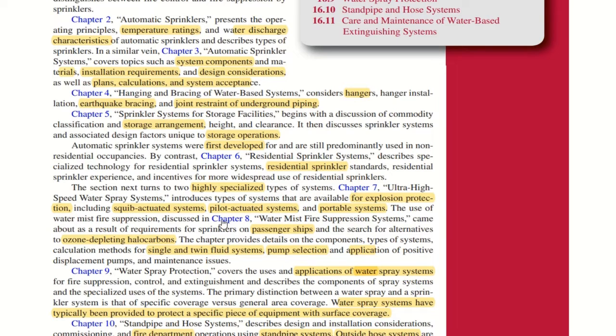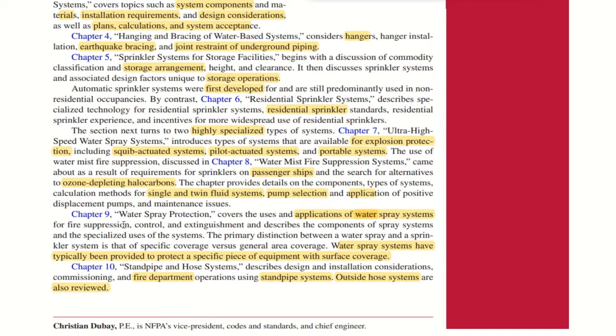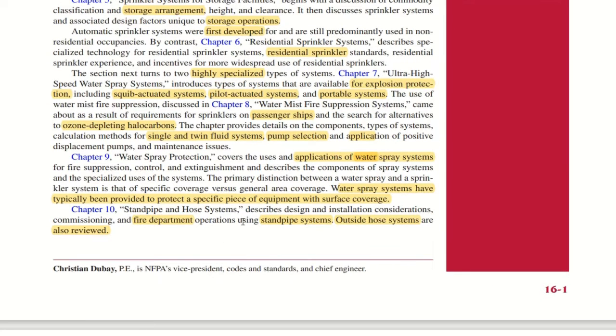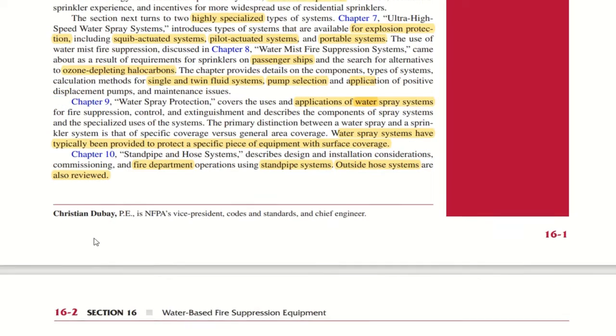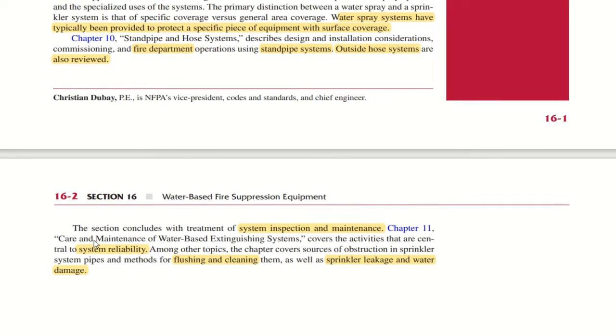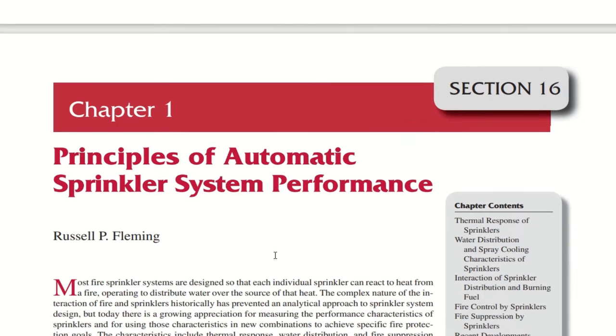The use of water mist systems is covered in chapter 8. Chapter 9 refers to water spray protection, which has typically been provided to protect a specific piece of equipment with surface coverage. Chapter 10 refers to standpipe and hose systems. Outside hose systems are also reviewed in this chapter. Finally, this section concludes with treatment of system inspection and maintenance. Chapter 11 covers the activities that are central to system reliability, and among other topics, it also covers sources of obstruction in sprinkler system pipes and methods for flushing and cleaning, as well as sprinkler leakage and water damage. So we will go through the important points in section 16, chapter 1.